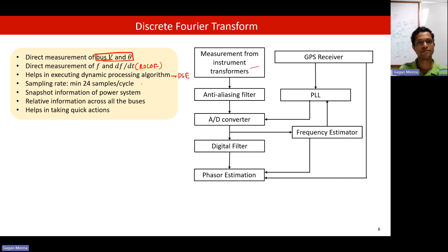PMU can also help us execute dynamic processing algorithms, like dynamic state estimation, because of its fast, high refresh rate - minimum 24 samples per cycle, that is one sample each 0.8 millisecond. We get an accurate, most recent snapshot of our system, along with relative information across all the buses, allowing us to take quick corrective or preventive actions.